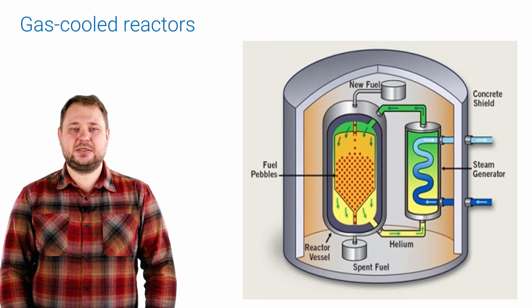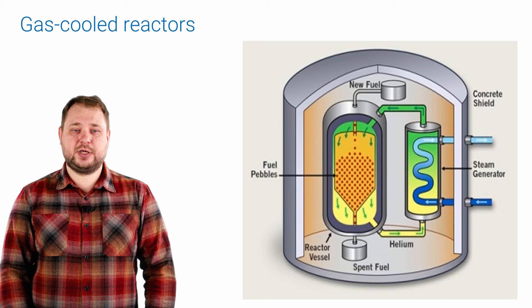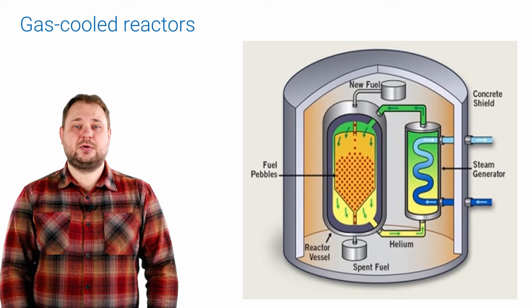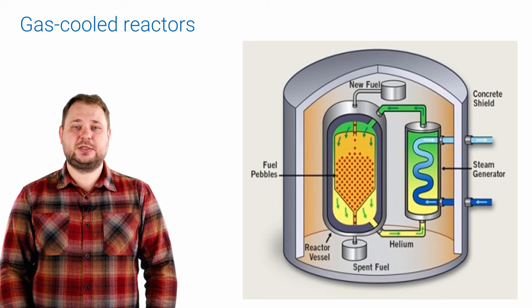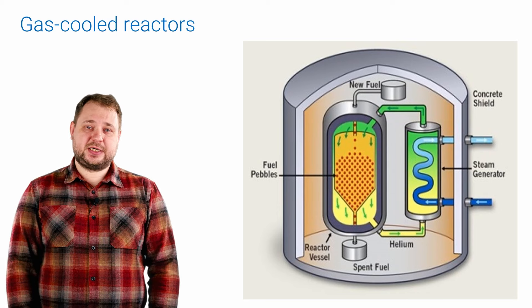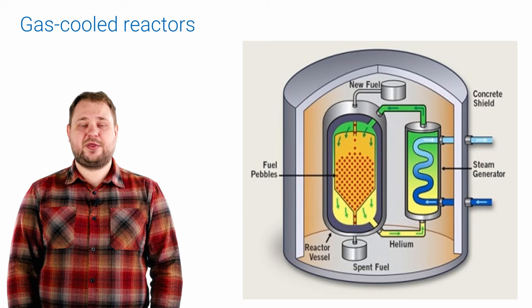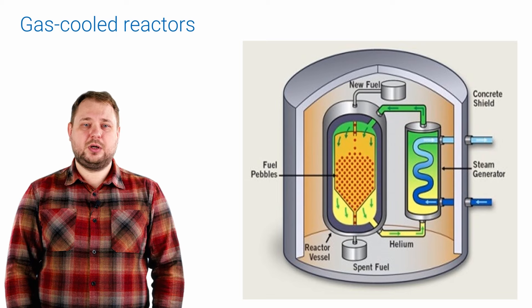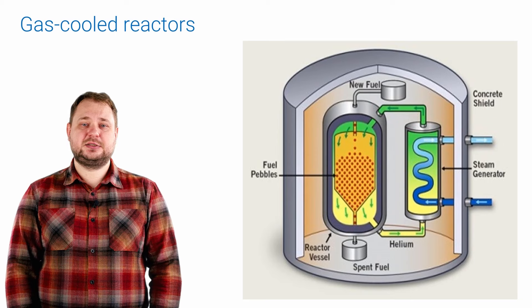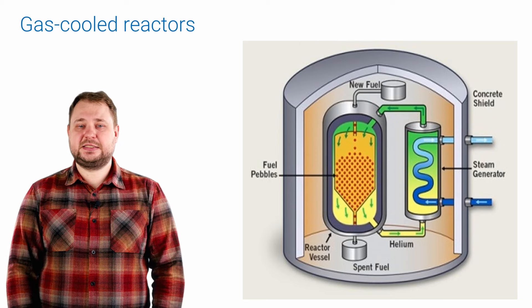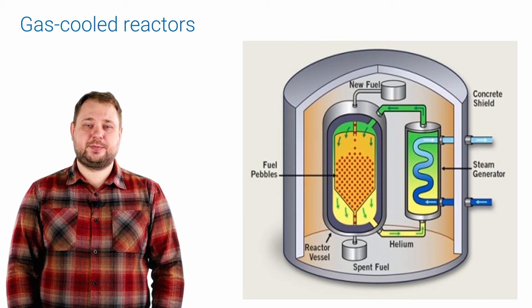The basis of HTGR is the reactor runs on tri-structural isotropic TRISO particle fuel. TRISO fuel consists of poppy-seed-sized particles containing uranium, carbon and oxygen. To contain nuclear products, the fuel is enclosed in three layers of carbon and ceramic shells. These particles are then formatted into cylindrical pellets or spheres the size of billiard balls, called pebbles. This fuel has increased strength and is more resistant to neutron irradiation, corrosion, oxidation and high temperatures.